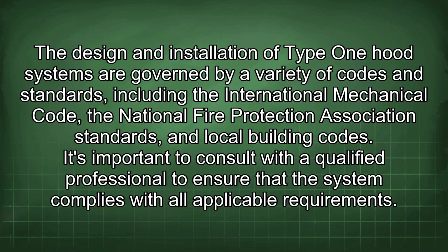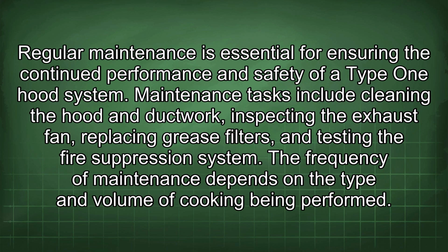The design and installation of Type 1 hood systems are governed by a variety of codes and standards, including the International Mechanical Code, the National Fire Protection Association standards, and local building codes. It's important to consult with a qualified professional to ensure that the system complies with all applicable requirements. Regular maintenance is essential for ensuring the continued performance and safety of a Type 1 hood system. Maintenance tasks include cleaning the hood and ductwork, inspecting the exhaust fan, replacing grease filters, and testing the fire suppression system. The frequency of maintenance depends on the type and volume of cooking being performed.